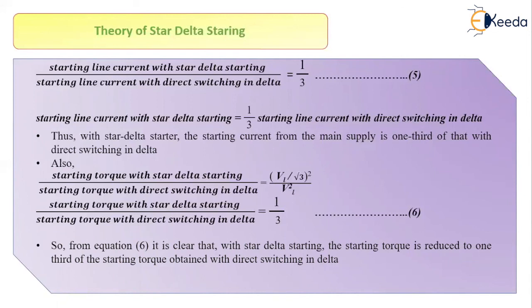In this way, we connect the motor in star initially and then in delta when it attains about 80% of the rated speed. Because of this connection, we reduce the starting current by one third and also reduce the starting torque by one third. Both high starting current and high starting torque are harmful for the induction motor, so to protect it we use star delta starting. The important thing to remember is that this type of starting cannot be used for star connected motors — it can only be done for delta connected motors. So the star delta starter is only used for delta connected motors. Thank you.